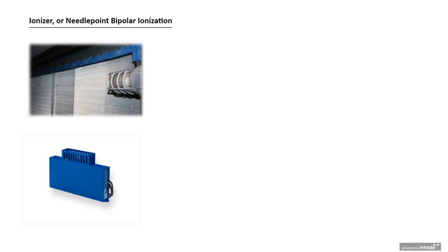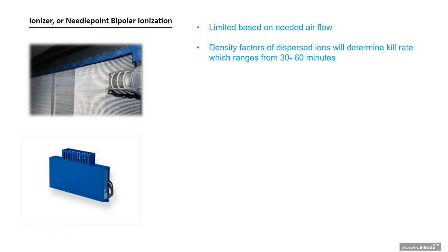The next technology is ionizers, or needlepoint bipolar ionization. This is a product that works. It is effective, but it's limited based on needed airflow. And what you see here on the left of this slide is this blue bar goes across the air handling unit. So typically, these needlepoint bipolar ionization systems will sit at the air handling unit, and it's based on how effective we are at pushing the air past these ionizers to drive the ions down through the HVAC system and then eventually to the rooms. However, the problem is there are density factors. The further away the ion gets from the generator itself, the less effective it becomes.